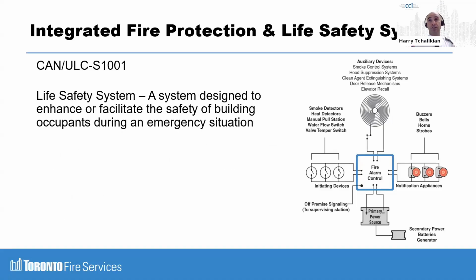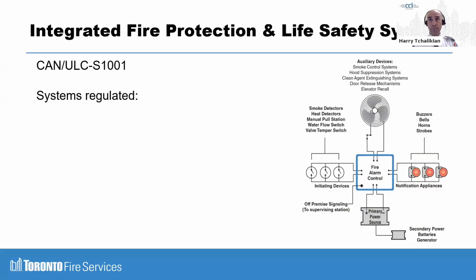And a life safety system is a system designed to enhance or facilitate the safety of building occupants during an emergency situation. So with this second definition, I did get clarification from the fire marshal's office that carbon monoxide detection systems that turn on your exhaust fans in new storage garages fall outside the scope of this, because that is deemed to be a domestic matter. So it's just something I got clarification from the fire marshal's office for that interpretation. So the system is regulated.